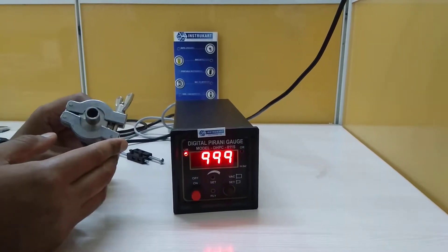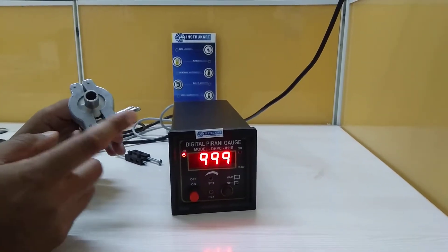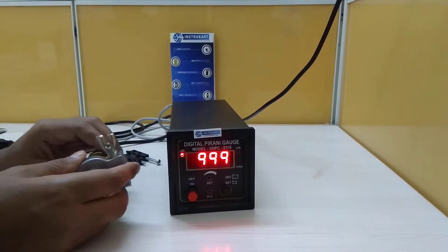of course for this KF10 clamp you can have an adapter for KF25 also. Sometimes KF25 clamp is also used that can be achieved with the use of adapter.